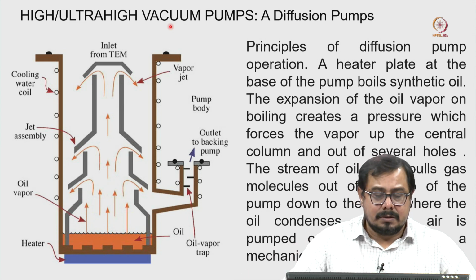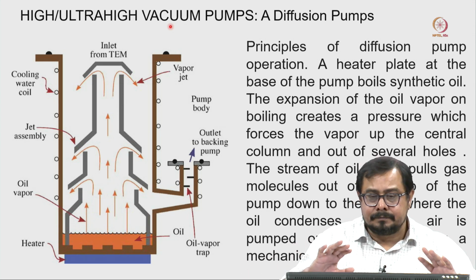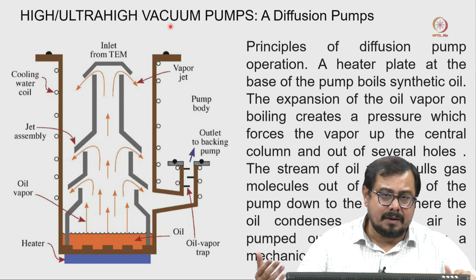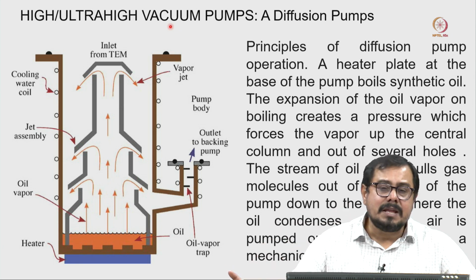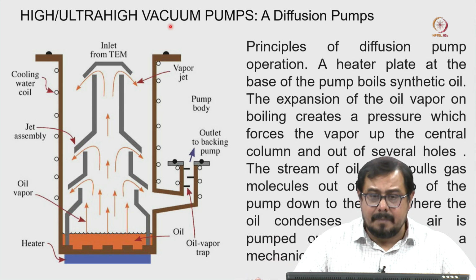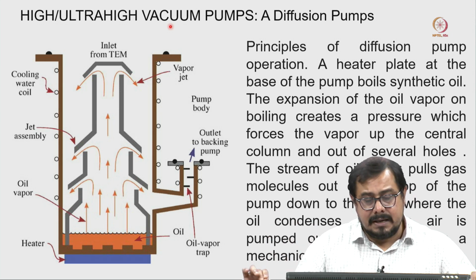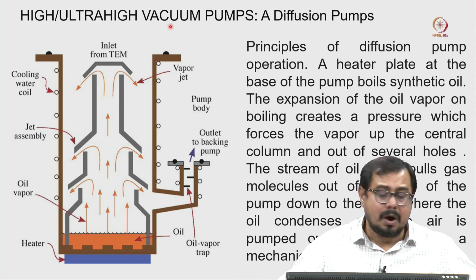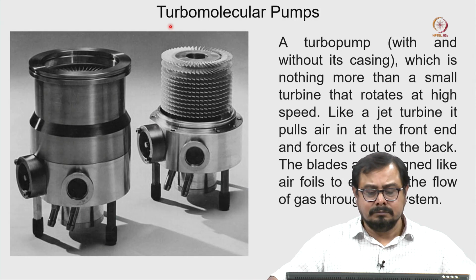That is one of the reasons this is not a very favorable pump nowadays for keeping high vacuum for the microscope. On the other hand, we are using the turbomolecular pump. The turbomolecular pump is a very good pump and we are using this pump to maintain a high vacuum. Let us take a look at how this turbomolecular pump works.